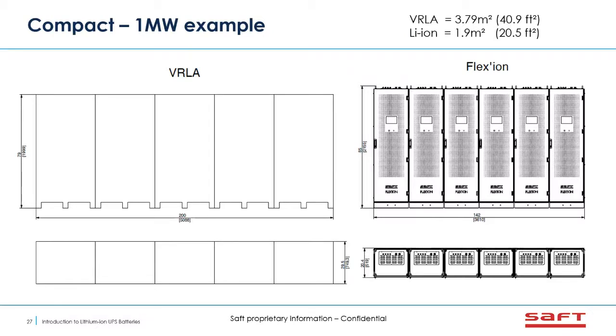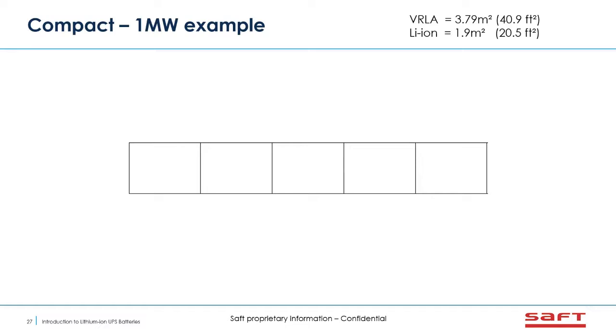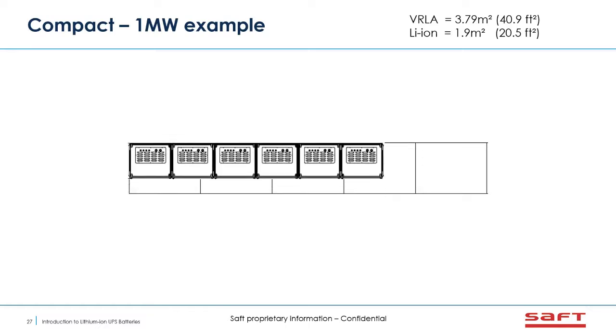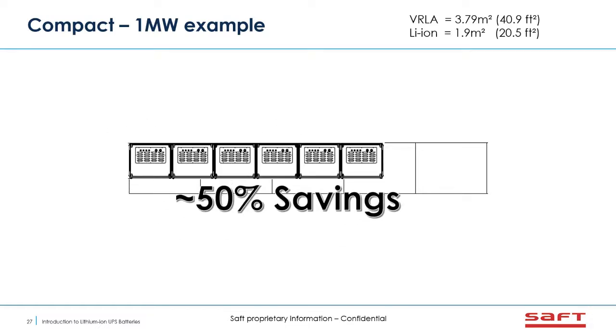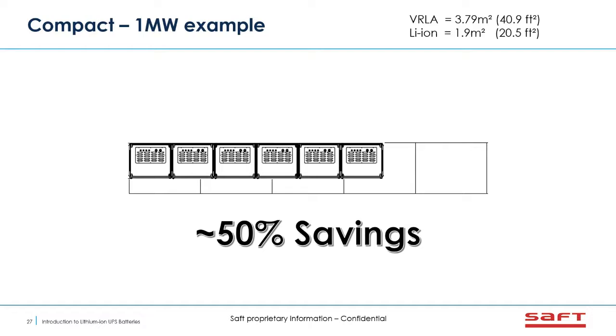Footprint, looking at a 1 megawatt example. This is a VRLA typical 40-inch cabinet. You have 5 of them to build the power up to 1 megawatt versus our Flexion system for Gen 2 would be roughly 6 cabinets here. So if we put them over each other, essentially what we have here is roughly a 50% savings on footprint. So that's a huge savings when you're designing battery rooms.